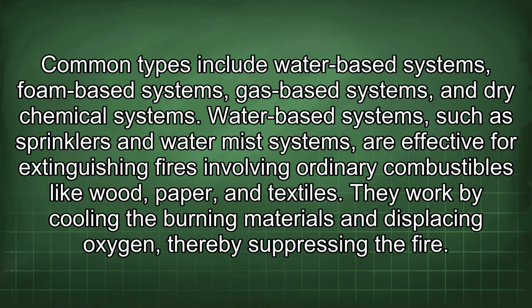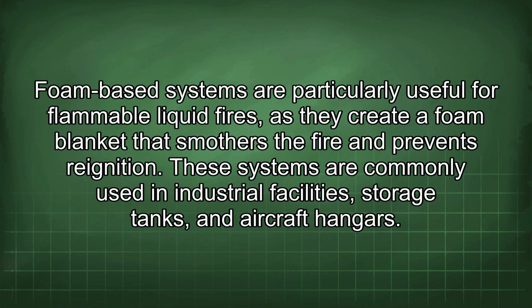Water-based systems, such as sprinklers and water mist systems, are effective for extinguishing fires involving ordinary combustibles like wood, paper, and textiles. They work by cooling the burning materials and displacing oxygen, thereby suppressing the fire. Foam-based systems are particularly useful for flammable liquid fires, as they create a foam blanket that smothers the fire and prevents reignition. These systems are commonly used in industrial facilities, storage tanks, and aircraft hangars.